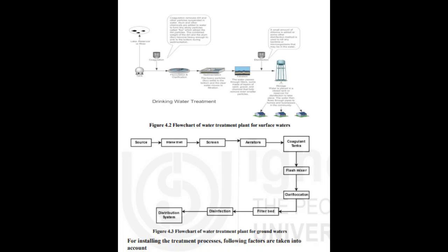Types of coagulants. 1. Aluminium-based: Al2(SO4)3, AlCl3, Na2Al2O4. 2. Iron-based: FeCl3, FeCl2, Fe2(SO4)3, FeSO4. 3. Hydrated lime and magnesium carbonate. Factors affecting coagulation: the type of coagulant used, the quantity of the coagulant, the time of mixing and method of mixing, and the characteristics of water such as temperature, pH, type and concentration of impurities.